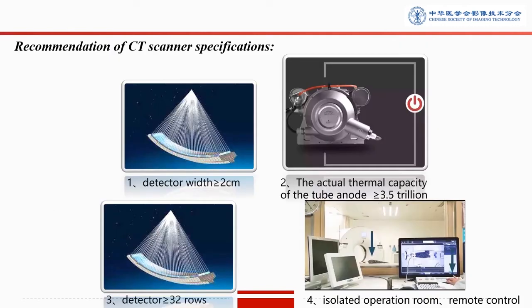Since the main job for the CT scanner in the makeshift hospital is chest scanning, the requirements are not very high. The detector width should not be less than 2 cm, and the actual thermal capacity of the tube anode should not be less than 3.5 MHU. We prefer a 32-row CT scanner or above. Most importantly, the CT scanner should have an isolated operation room to keep the technologist in a safe area, and it would be ideal to have a remote control system, which is also helpful for infection control and prevention.